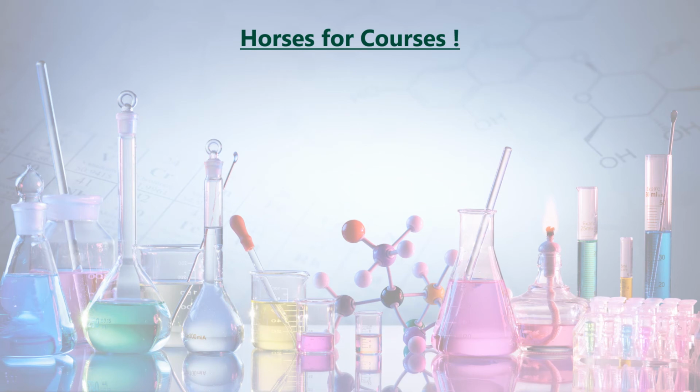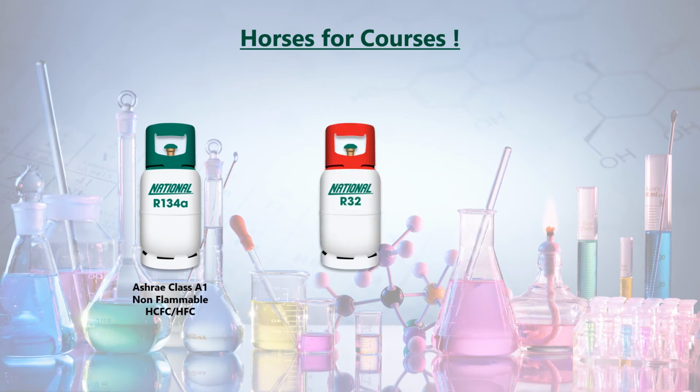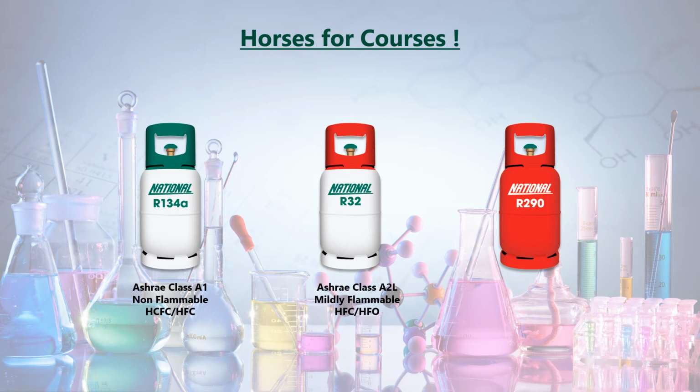Here at National, we supply 3 specific refrigerant types: ASHRAE Class A1, non-toxic, non-flammable, standard HFC, HCFCs. ASHRAE Class A2L, which are non-toxic, mildly flammable HFC and HFOs. And thirdly, we have ASHRAE A3, which are highly flammable hydrocarbons. If you are in doubt about refrigerant types, please visit our product section of the website. Each refrigerant is easily identifiable by its cylinder image colour. All white body with a green shroud denotes A1, non-flammable standard refrigerant. All white cylinder body with a red shroud denotes A2L, mildly flammable refrigerants. And then the all red cylinders are A3, highly flammable.